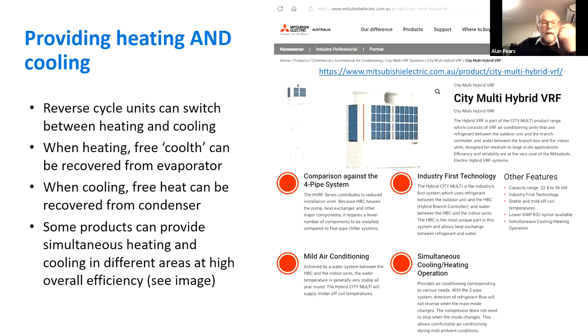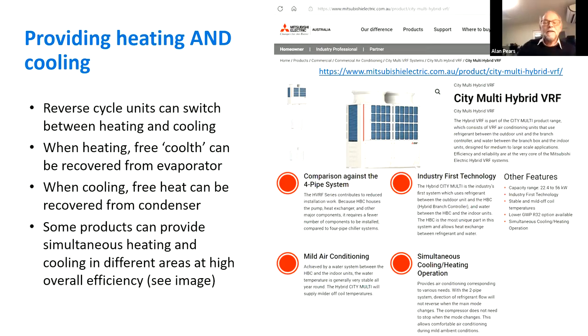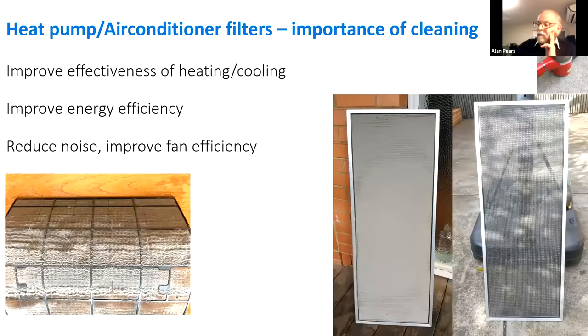Heat pumps can also do lots of things in terms of simultaneous heating and cooling. A reverse cycle air conditioner can switch between heating and cooling by running backwards. If you're running a heat pump for heat, there's essentially free cooling coming off the other side. Conversely, a chiller producing cooling also produces heat that can potentially be used. Some newer products can actually provide heat in some parts of a building and cooling simultaneously in other parts, giving really useful overall efficiency improvements.